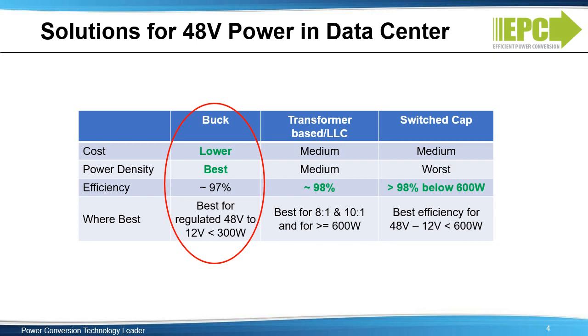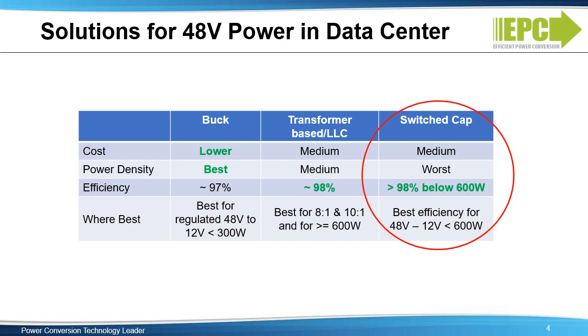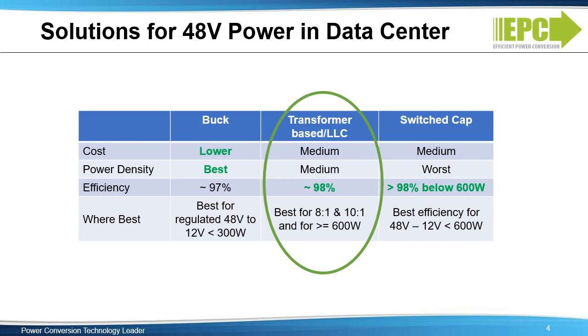However, for higher power, thermal handling and inductor size can be a challenge for the buck converter. The switch cap is inexpensive and very efficient at 48 to 12 volts when under 600 watts, but it is much more complicated than the simple buck or LLC. Also, the switch cap has limitations at high current and is not really a practical solution for systems greater than 600 watts. The LLC offers the best efficiencies for power levels greater than 600 watts for both 48 volts to 12 and 48 volts to 6 volts, and is the best topology for Vin-to-Vout ratios of 8-to-1 or 10-to-1.